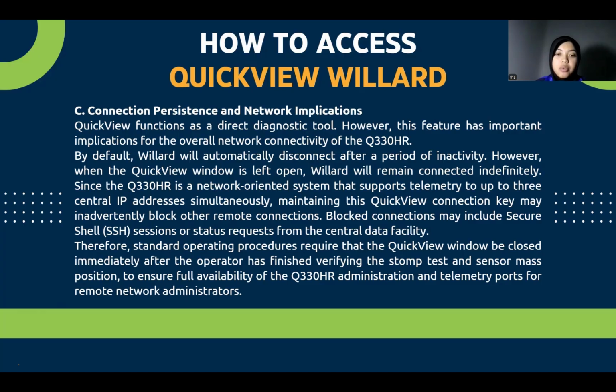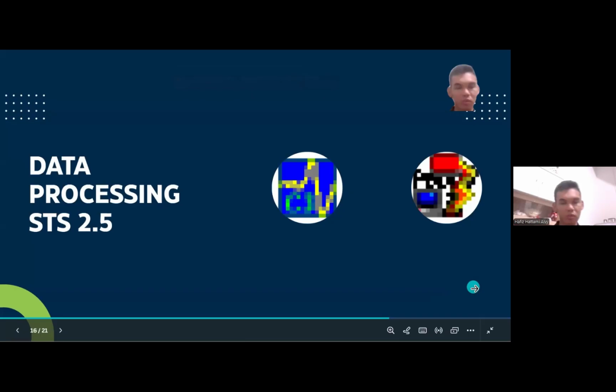Therefore, standard operating procedure requires that the quick view window be closed immediately after the operator has finished verifying the stomp test and sensor mass position, to ensure full availability of the Q330HR administration and telemetry ports for remote network administrators.